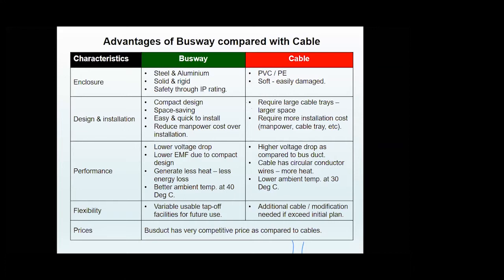Price-wise, busway in low ampere ratings is more expensive than cable in terms of material cost. However, when you compare busway and cable price, you need to consider the overall cost — material, installation cost, and support structure cost. Cables require more manpower and larger cable trays for higher ampere ratings, whereas busway only uses a C-channel and hanger rod. Overall, especially in high ampere ratings, busway prices are very competitive compared with cables.